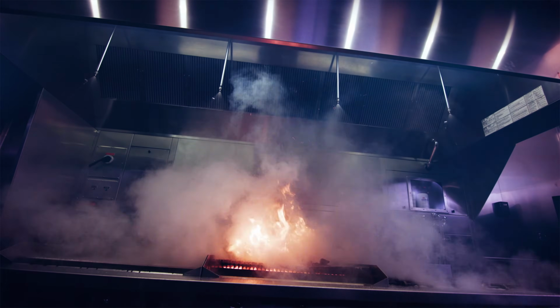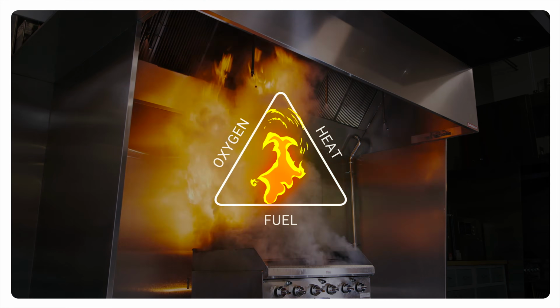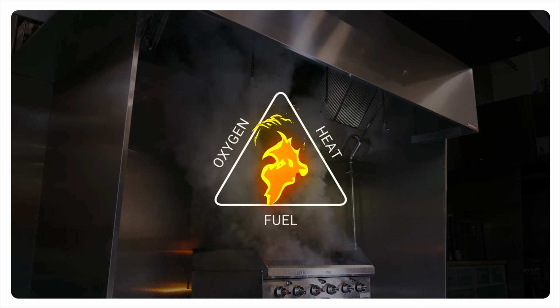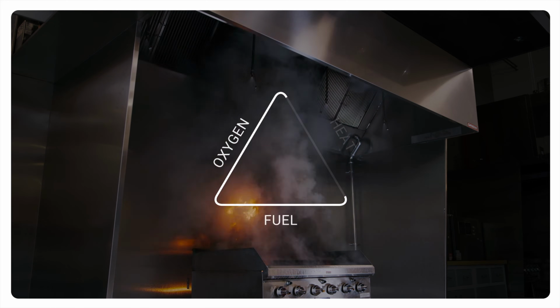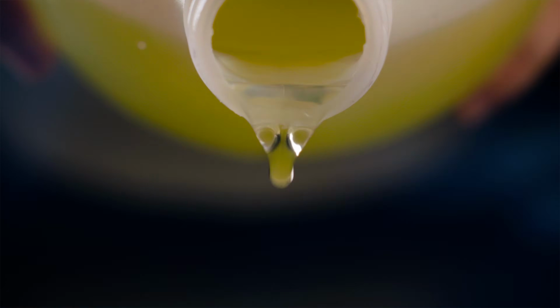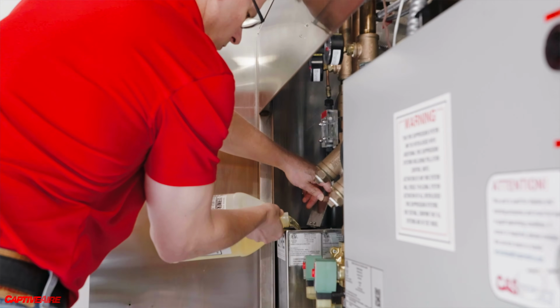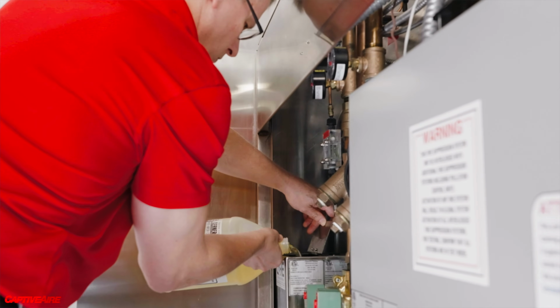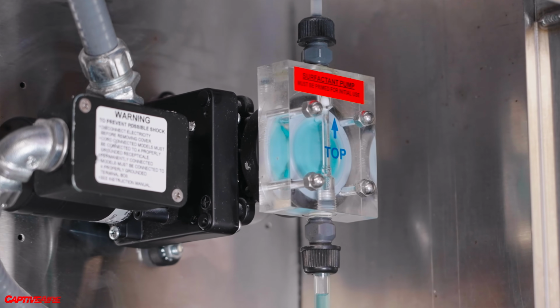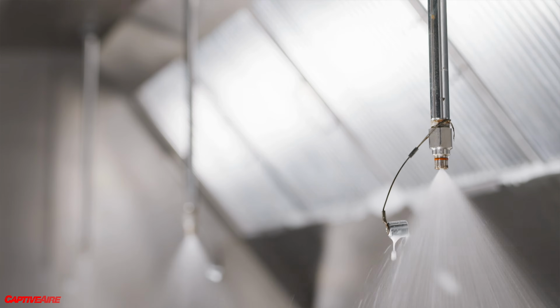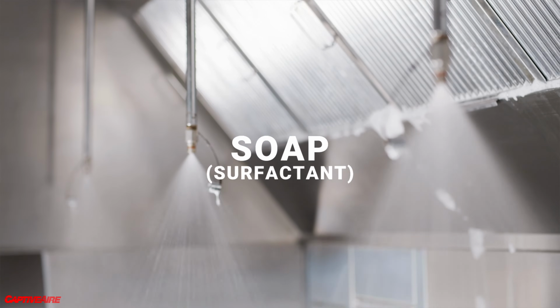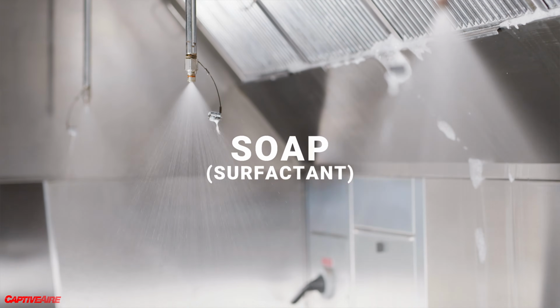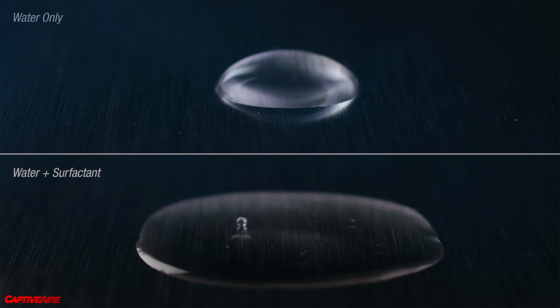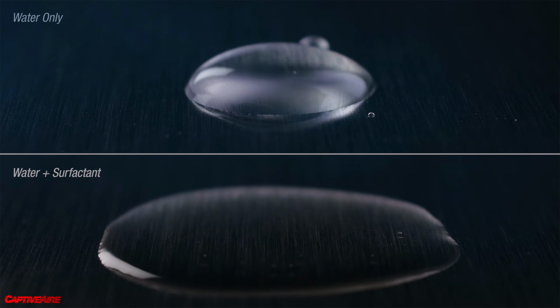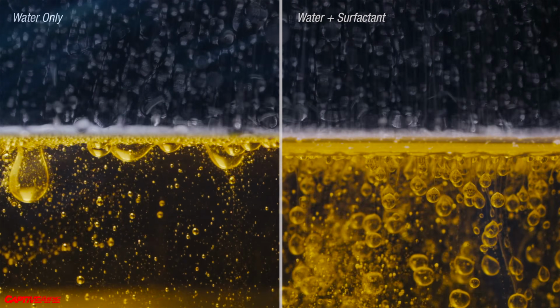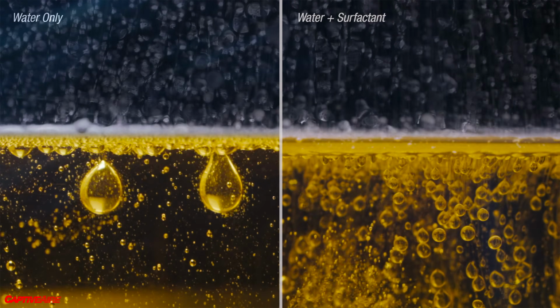Unlike wet chemical systems, Core doesn't even try to smother the fire. Instead, it relies on an endless ability to cool the fire and put it out. On top of that, Core still mixes a chemical with the water, but instead of a corrosive salt, it uses something more familiar - a simple soap, often referred to as surfactant. By injecting the surfactant into the water, we reduce the surface tension between the water and the grease itself, helping the water interact with the grease better.